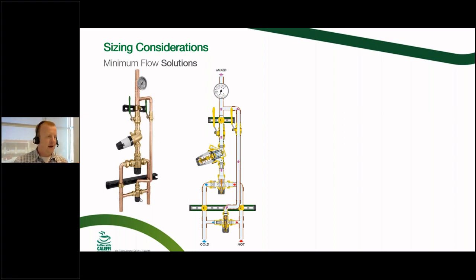And this is where a lot of times good intentions fall flat on their face. The big thing here is that you have to be able to set up this pressure reducing valve to open at the correct time, or at the correct pressure drop. And so there's actually a procedure, and it's not quite as intricate as the recirc balancing that we talked about earlier. But the fact is that you've got to set this guy up, and you've got to produce a demand in multiple scenarios and have certain valves valved off and things like that.